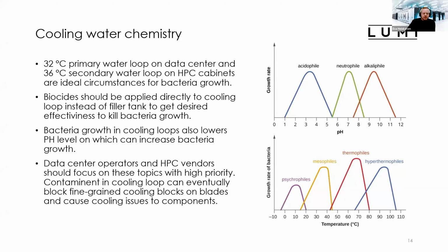Then the last slide is about the cooling water chemistry. This 32 Celsius inlet on the primary loop, which we are running on the data center side, and 36 degrees on the secondary water loop in the HPC cabinets are ideal circumstances for bacteria growth. As you can see, this mesophile bacteria growth is at its highest at these temperatures, 32 to 36 degrees. So based on this graph it would be best to have a little bit over 40, about 45 degrees, to decrease the bacteria growth in these cooling loops.